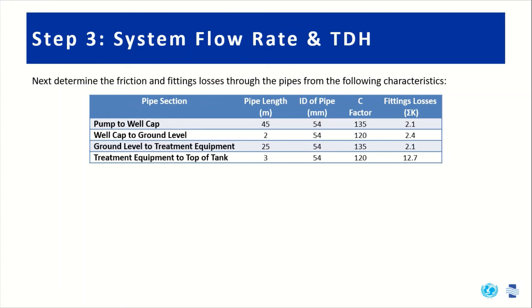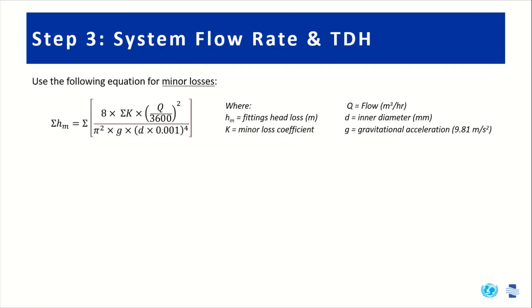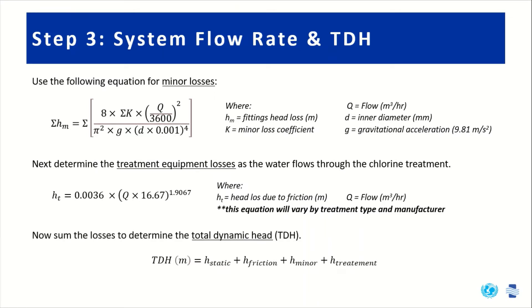This table shows the various pipe lengths, pipe diameters, C factors, and fitting loss sum-of-coefficients for different sections of piping in our system: from the pump to the well cap, the well cap to ground level, ground level to treatment equipment, and treatment equipment to the top of tank. Equations are shown for calculating friction losses and minor losses — hit pause if you'd like to look at those in more detail. There is also an equation for treatment losses. Finally, we add all of these losses together to determine our total dynamic head.